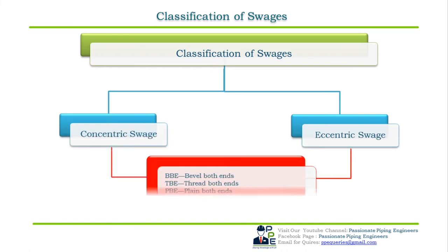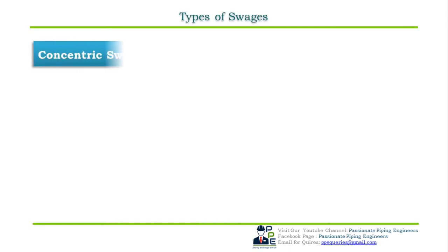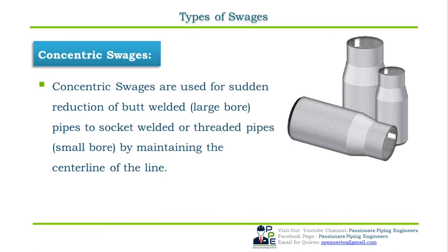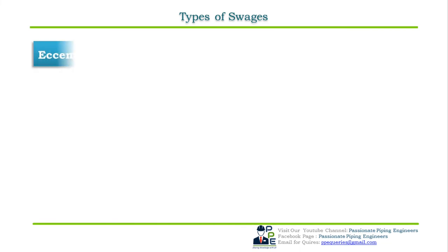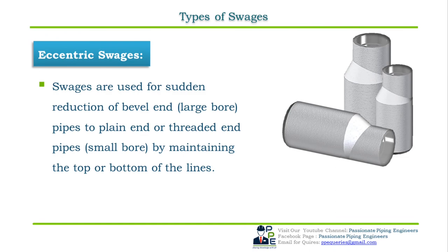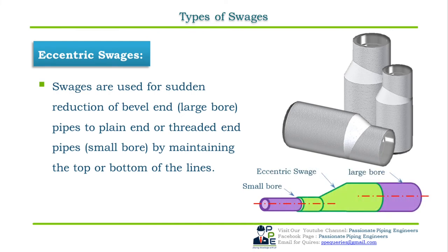Similar to reducers, swages are available in concentric and eccentric shapes, further divided by end preparations. Concentric swages are used for sudden reduction of butt welded (large bore) pipes to socket welded or threaded (small bore) pipes while maintaining the centerline of the two connecting pipes, as shown in the figure. Eccentric swages perform the same reduction but maintain the top or bottom of the two connecting lines.